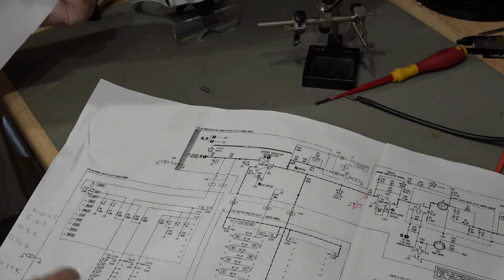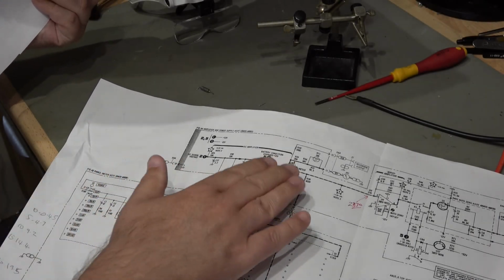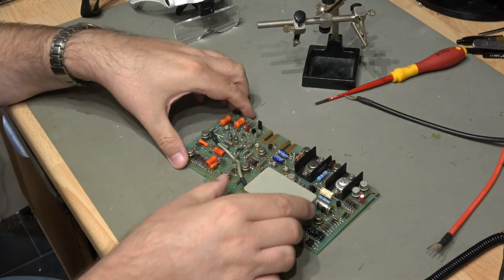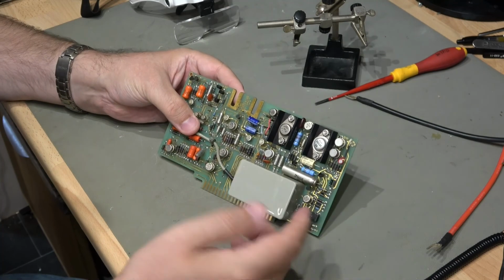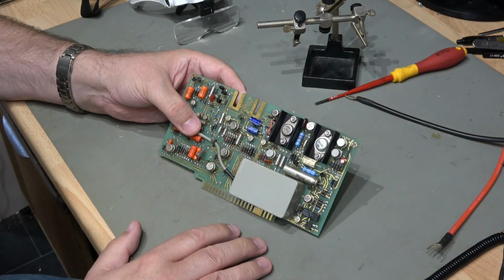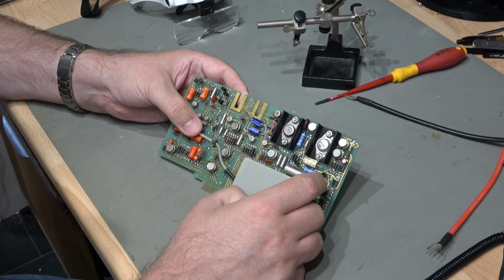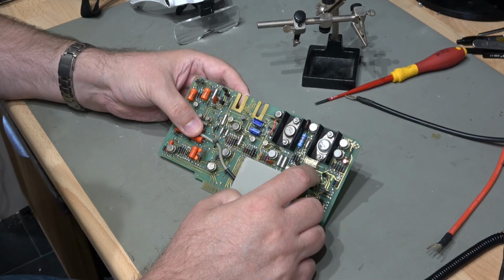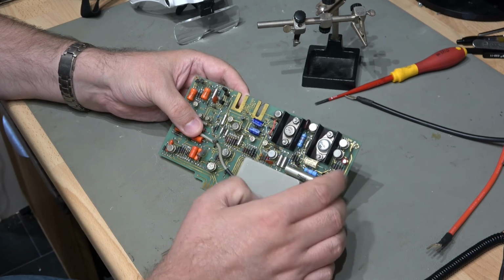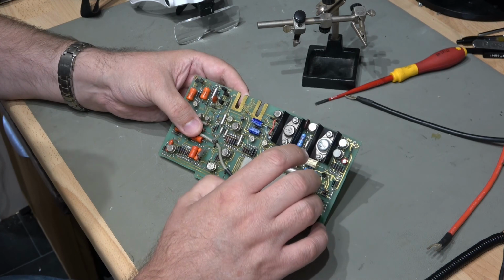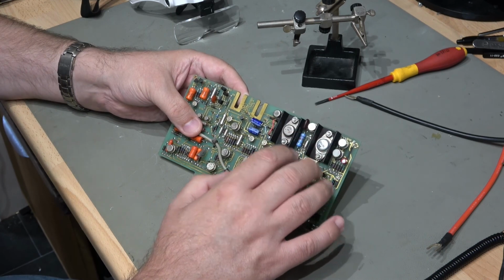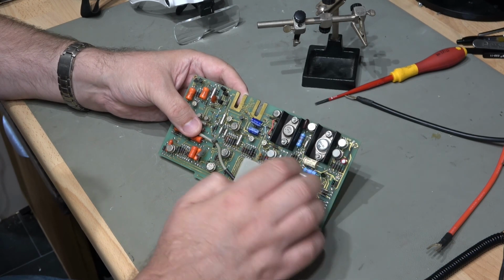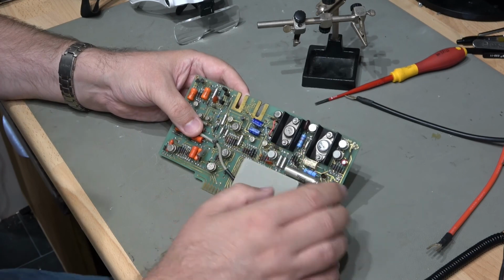The likely place is on this next switch section, which has some capacitors, so that could well be leakage, and of course there could be capacitors elsewhere. So I'm actually going to take a moment now. I'm going to pop out all of the capacitors one by one. I'm going to test them, and I'm just going to work my way through all these tantalum capacitors, seeing if they're in range or if they're actually leaking. There is a good possibility that some of them are leaking, and I'll have to do my tests quite carefully to differentiate those. I suspect most of the capacitors will be okay, except for leakage current. So I'll measure it on my capacitance meter, and also by putting a voltage through and measuring the leakage current using a sensitive multimeter.